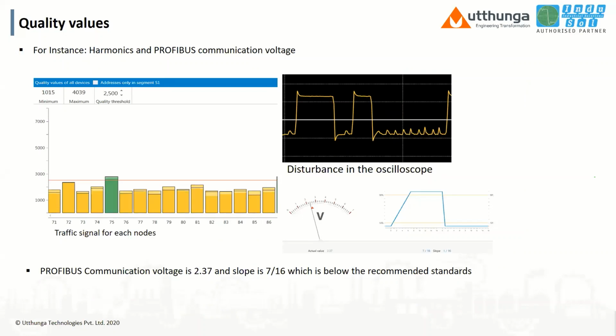So this is a real case scenario. When we analyzed one of the plants, you can see the voltage is showing complete yellow. That is below the threshold. This is the threshold, 2.5 volt. Completely all the nodes are below 2.5 volt. And the voltage you can see is 2.37 and the slope is 7/16. Moreover, you can see the interferences, the harmonics are very bad.